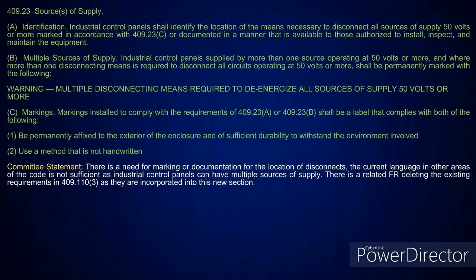All right, I'm not going to go through the committee statement there. Now this is 409.23. This is where you're getting into your industrial equipment, and they made a few changes here. They're making it clear that there is going to be a need for you to have marking or documentation for the location of the disconnects. Because the way it is right now, you can go look in other articles, but there isn't enough language there to take care of the multiple sources of supply that are here. True. Because you're dealing with industrial control panels. Yeah. So what they did, they incorporated everything right here and tell you about the identification.